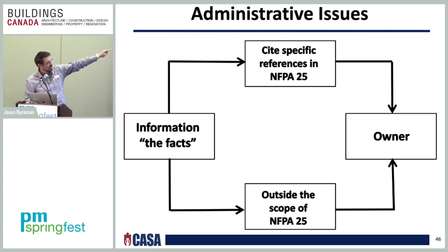That information is site-specific. So there's two different things, that site-specific that references the NFPA 25 in your inspector forms, or it's outside the scope of NFPA 25, which would be basically an informational-only report, which is basically a report that stipulates that you have design or installation issues on your system. So the top, site-specific, is you have operational problems. And at the bottom, you have either design or installation problems. That is all given to the owner. And that owner or owner's representative has to keep those records. And in NFPA 25, those records is three records. The record for acceptance, the record previous, that was the previous record, and the current record needs to be maintained, and basically the owner shall have that.